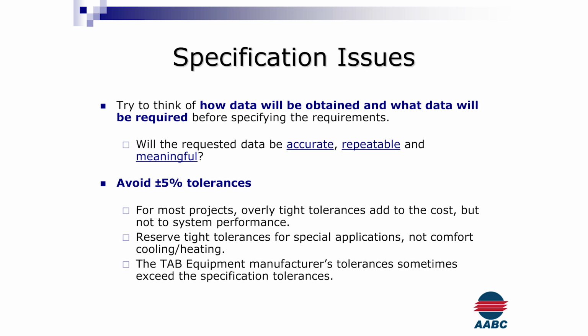A lot of the times, the engineers and the people approving the submittal or the equipment aren't necessarily always looking at what the capabilities of the equipment are. In some cases, VAV boxes have a plus or minus rate of 14%. If that's the case, there's no way that as a balancer I'm ever going to get a plus or minus 5% balance at the outlets. That's just one example of what we're hoping to see when we get there, so we can hopefully have a balanceable project and not come up with 3 or 4 issues before we've even finished our balancing plan or procedure.